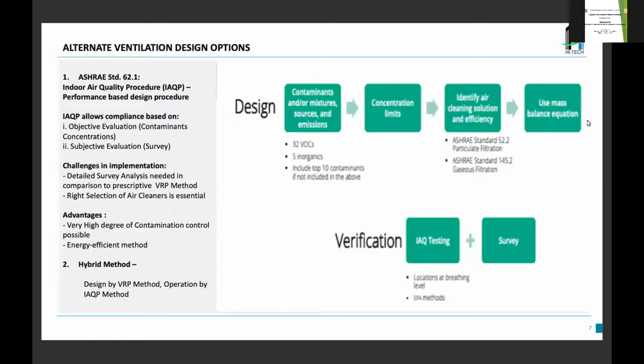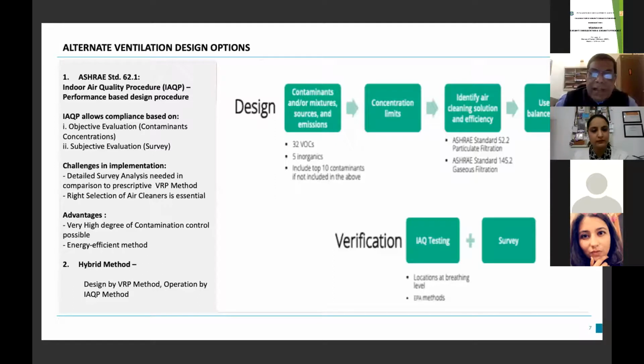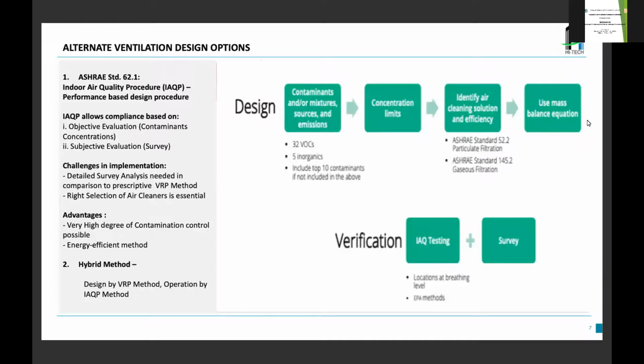Design has been done by the VRP method, and operation of the system is done by the IAQ method calculations. Because the IAQ method will require lesser outdoor air compared to the VRP method, in that case you have the flexibility to increase the outdoor air supply up to the maximum, the minimum air requirement.